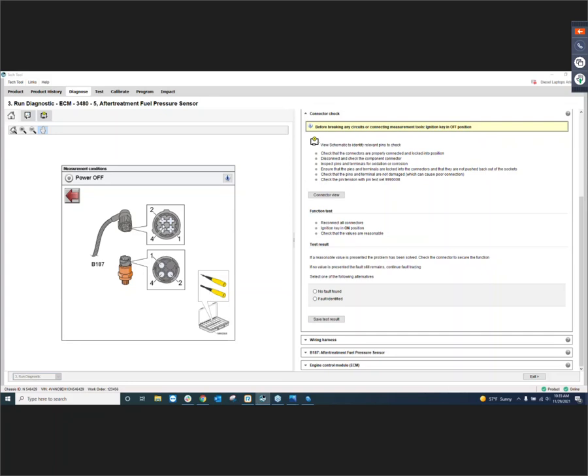What you're going to do is use your pin kit, select the right size pins, and check the connectors. Make sure you've got good drag. Unfortunately, once the female connector is connected to the male side, you're not going to be able to check if they're making good contact. Typically you can see if they've been arcing - there might be some discoloration on the pins - but nothing beats feel. Put the pin kit on it, do your drag test, drag the pin across the connector, and make sure you're getting a good connection.